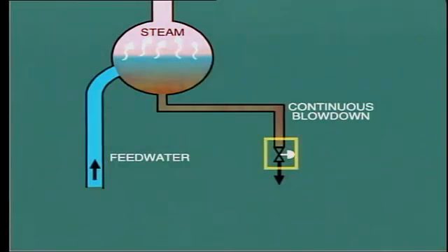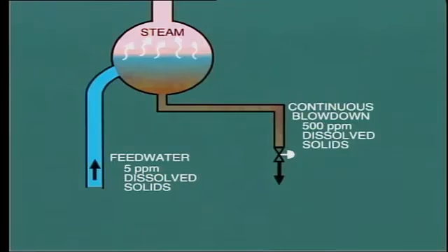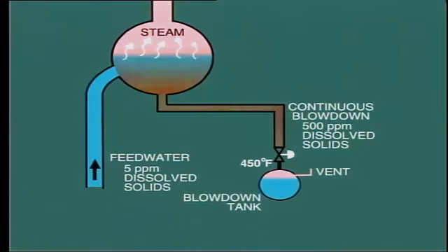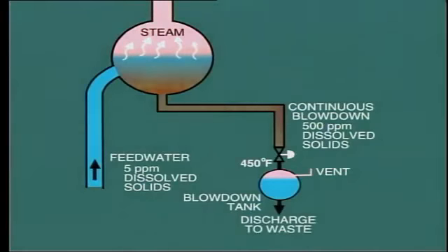One method to reduce the concentration of solids is by continuous blowdown — a regulated quantity of water discharged from the bottom of the drum to waste. A control valve is fitted to allow regulation of the quantity of continuous blowdown. The blowdown water may contain 500 parts per million of solids, and this is replaced by boiler feed water which contains perhaps 5 ppm — resulting in dilution with consequent reduction in total solids concentration. As the blowdown water is at relatively high temperature between 400 and 500 degrees Fahrenheit, it is discharged into a blowdown tank. This permits some of the high-temperature water to flash off into steam and be vented to atmosphere, with the remaining water discharged to waste.